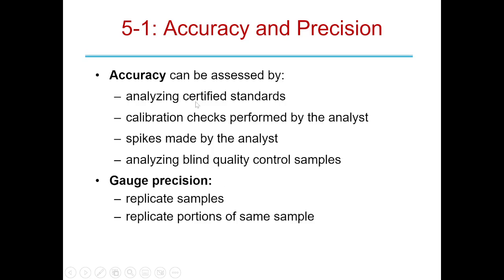By the way, every instrument should have a certified standard that they keep near the instrument, and you would just put it on and test it at a given time during the day. If you start drifting off, then you can calibrate to that standard, okay? And you may have to remake them if they're liquid, but typically they try to make them solid, something durable. Even the balances have that, you know that, right? Even the balances come with standards.